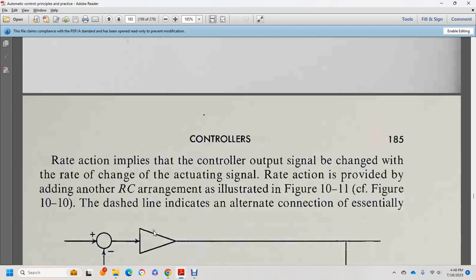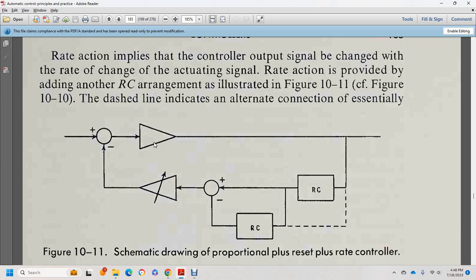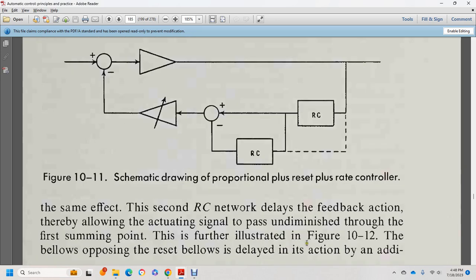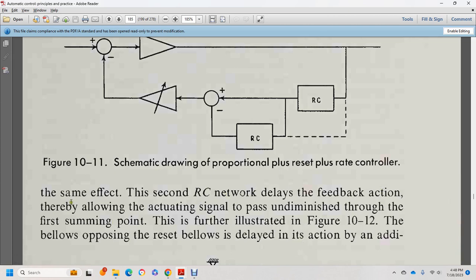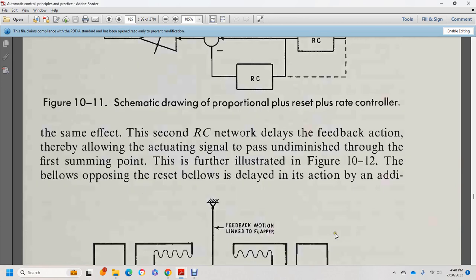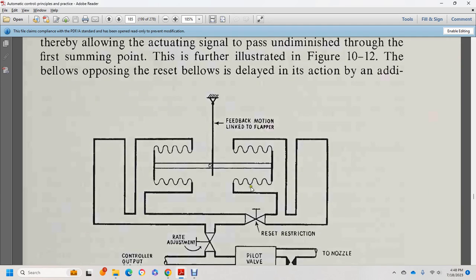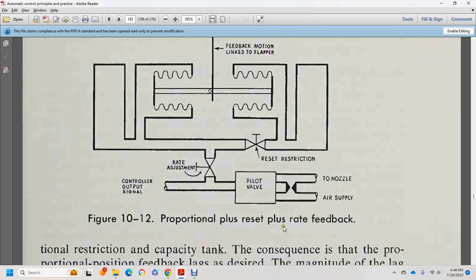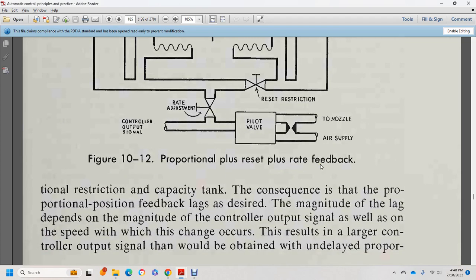Rate of action with another RC network has been introduced, illustrated in figure 10-11. The schematic diagram of proportional plus reset plus rate controller uses an RC network delay with the feedback action, allowing the actuating signal to pass undiminished to the first summing point. As further illustrated in figure 10-12, the reset bellows action is delayed by additional feedback motion linked to the flapper, with reset restriction, rate adjustment, control output signal, and pilot nozzle.